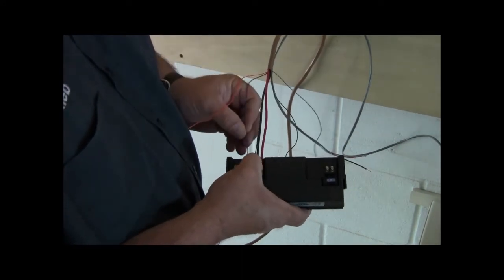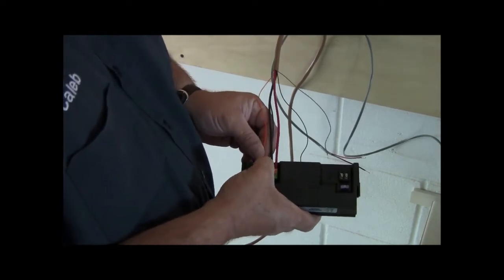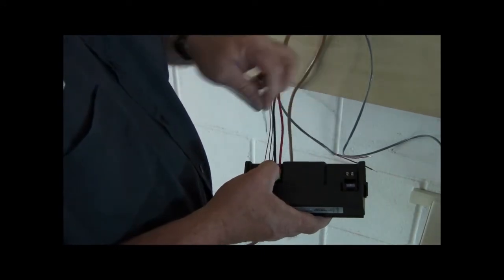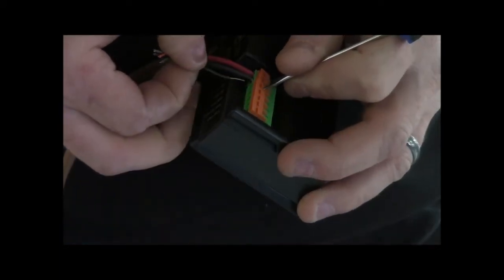Pull back the orange tab on each of the spring cage connections fully and push the wire in the opening. Release the orange tab and pull back slightly on each wire to seat the grip as you move across the connector. The spring cage tab can be pulled back with a fingernail or small screwdriver.